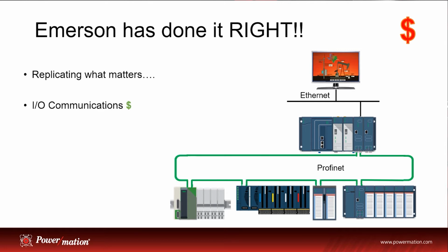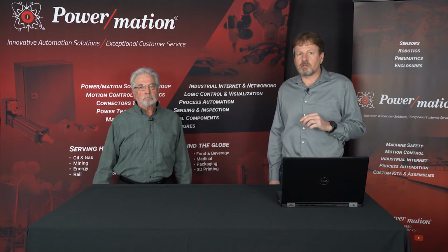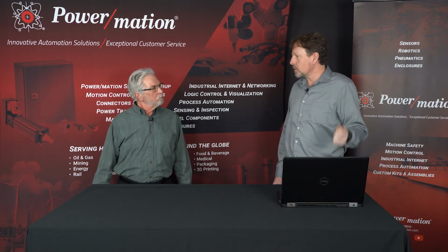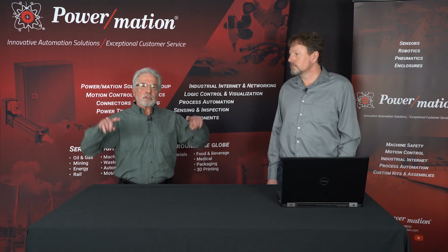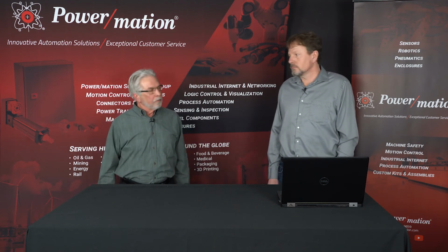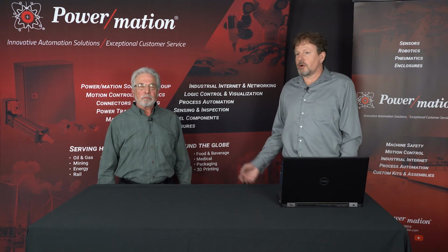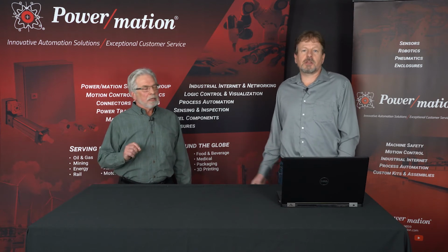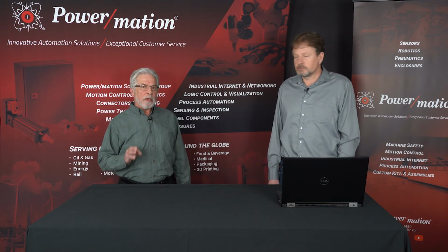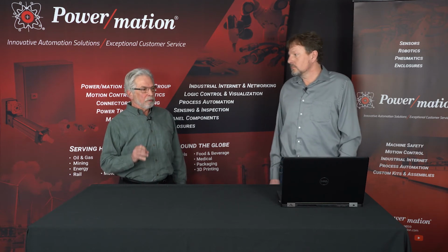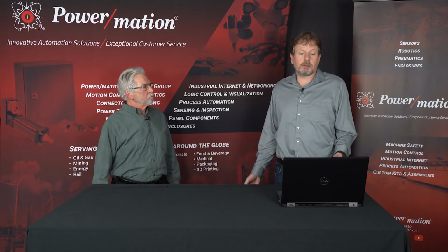So first is I/O communications. That's pretty low cost. That's already built-in redundancy on the networking, so you just complete the wire. Yeah, so we're talking about a redundant ring where it's self-healing. Correct. If we get a break in that cable, the communication will just wrap around in the other direction and everything will stay up and happy and keep running. And the cost is a cable, and the cables are inexpensive. Yeah. So an inexpensive add of a cable increases the availability of that system significantly. Yep, because you could break a wire.